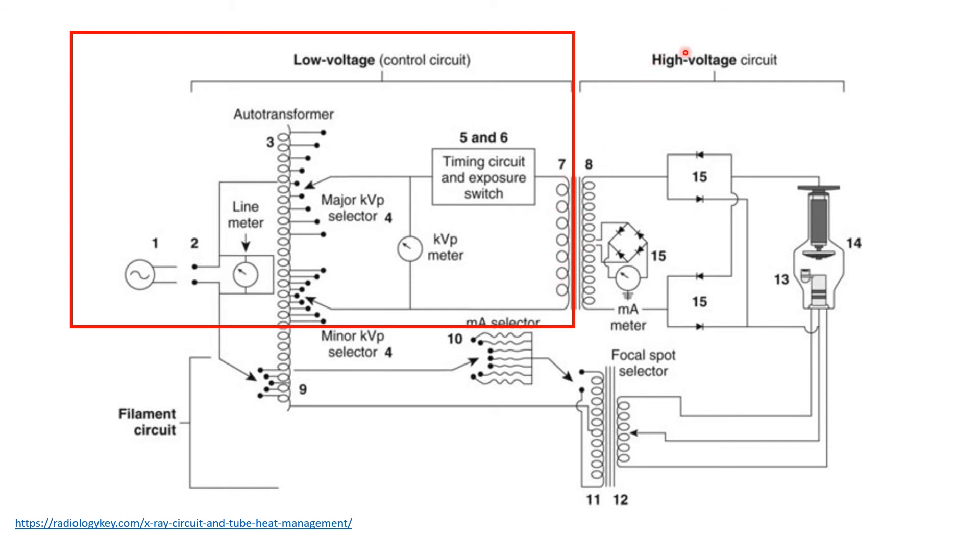Last, the exposure timer, 6, is the device that stops the exposure and is set by the operator on the control console.